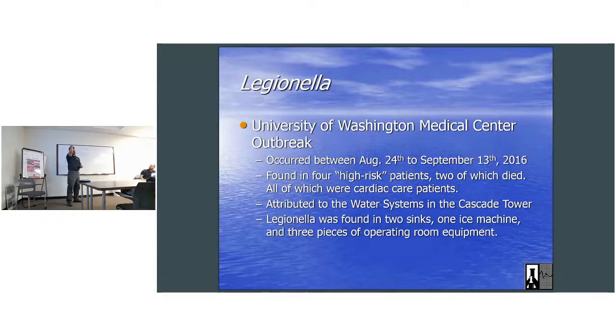And so again, with the ASHRAE plan, you don't actually have to test. But most of them are making it a standard protocol in at least the next couple of years. And I can see it: if you just say, hey, I tested it annually and I came up negative, you have a way to explain away a process that's happening. Even with that, they don't want you treating a system with pure acetic acid and immediately testing it the day later. They want you to test it 3 days later. They have a whole protocol for it.